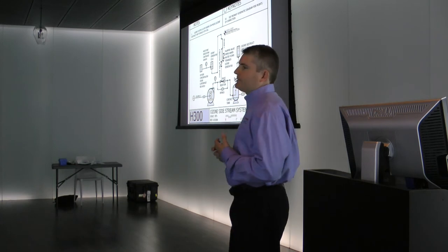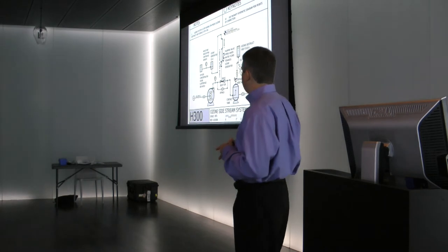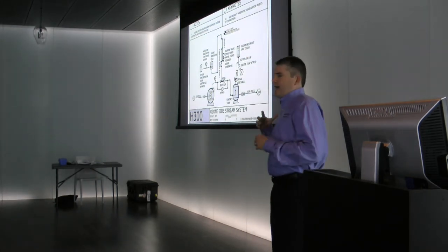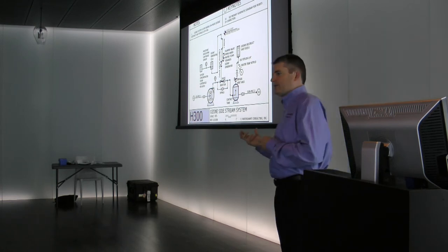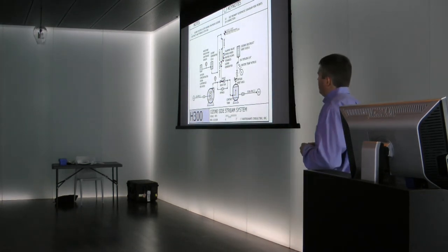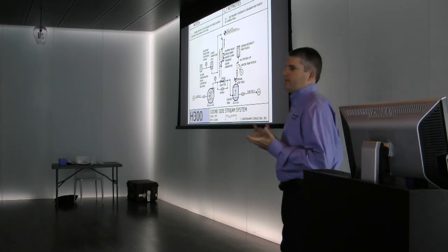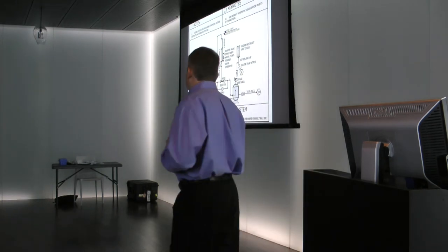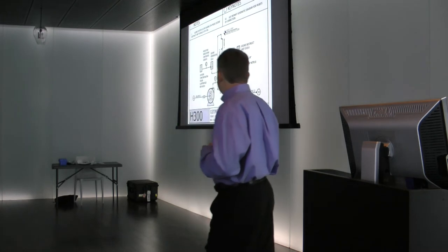The frequency of the injection? It's continuous. Yeah, the ozone generator, because the half-life is measured in seconds, you have to generate it on site. You can't produce ozone and then truck it somewhere in a bottle. You generate it right on site. One way is with the UV systems. I prefer the corona discharge. The concentration's a little higher, and I think the systems last a lot longer with proper maintenance.